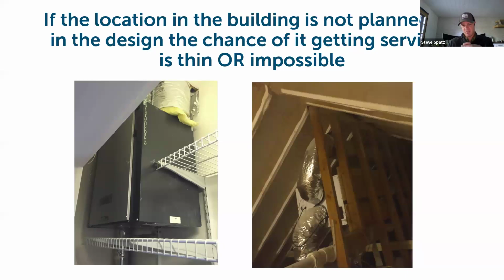So they need to be accessible, and the homeowner needs to be aware that they need to be maintained. This is another example where this is a closet, and this is a closet header here, and there's the cabinet door of the ERV that needs to be opened. And these are both one-and-done ventilation systems, where they will run until that filter needs to be cleaned and maintained. And once it gets to that point, since there's no way to access that filter, you no longer have a ventilation system running in the building.